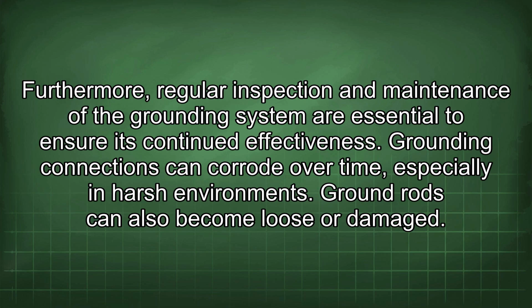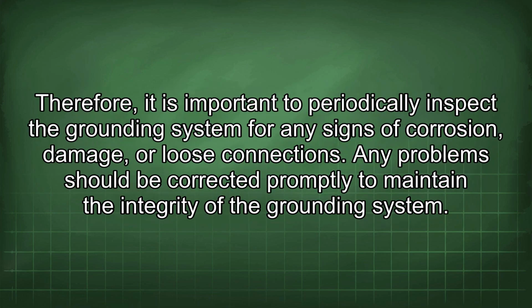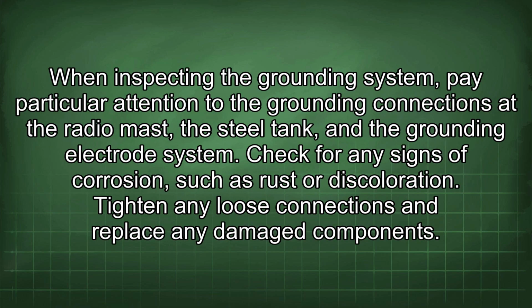Grounding connections can corrode over time, especially in harsh environments. Ground rods can also become loose or damaged. Therefore, it is important to periodically inspect the grounding system for any signs of corrosion, damage, or loose connections. Any problems should be corrected promptly to maintain the integrity of the grounding system. When inspecting the grounding system, pay particular attention to the grounding connections at the radio mast, the steel tank, and the grounding electrode system. Check for any signs of corrosion, such as rust or discoloration. Tighten any loose connections and replace any damaged components.